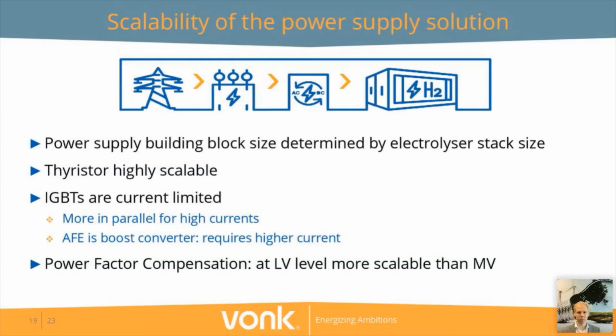From a technology point of view, thyristors are highly scalable. They are very well suited for dealing with high currents. IGBTs, however, are current limited by nature. In practice, this means that you need to apply more IGBTs in parallel to achieve the same high currents as you would have with a thyristor solution.